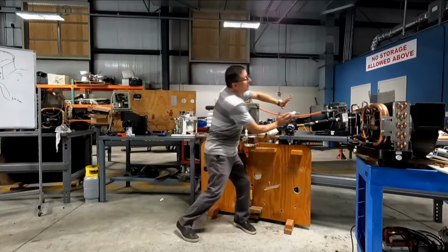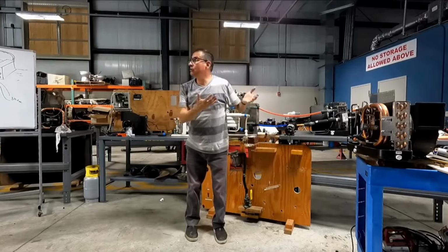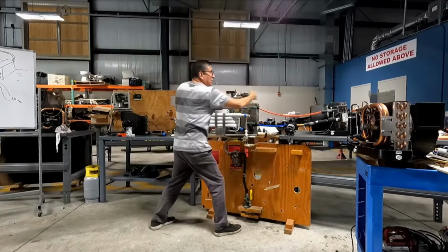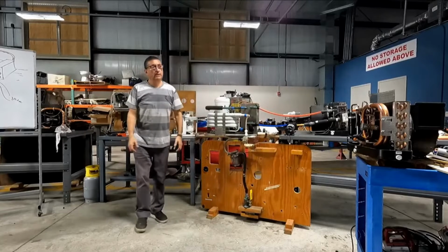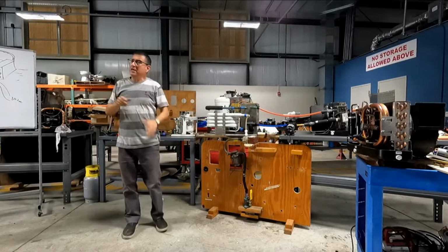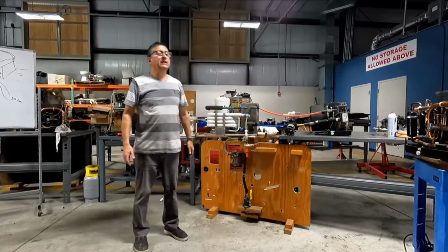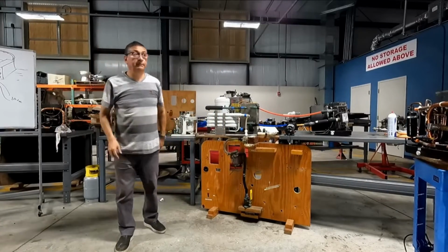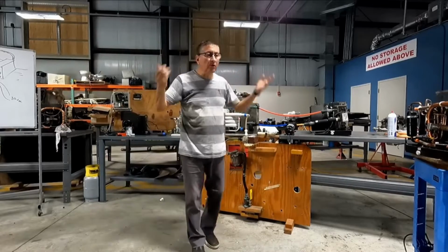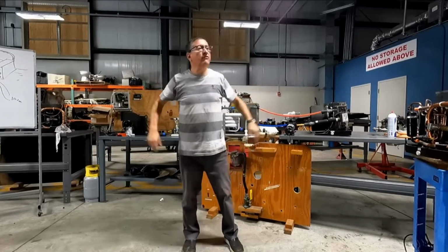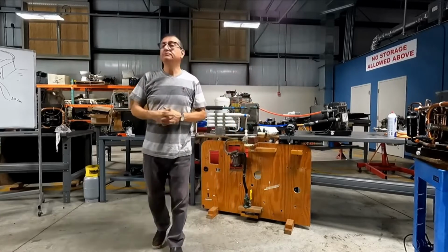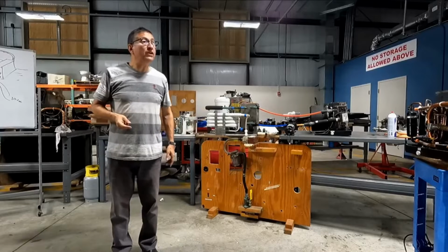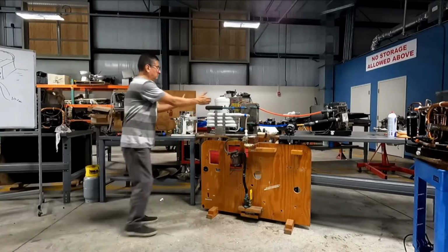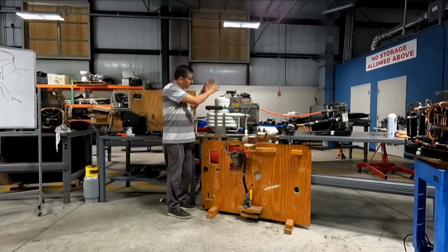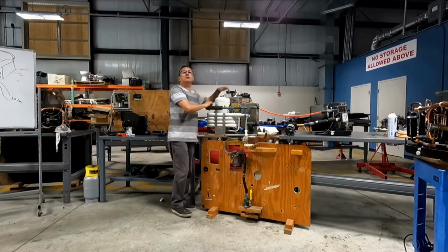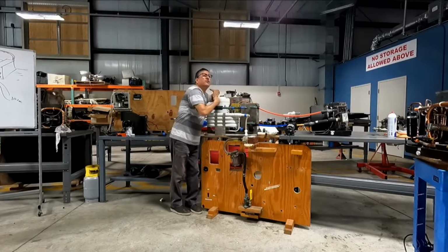What's the advantage? What is the name of that unit? Air handler. And what is the name of this complete unit? Chiller unit. The chiller system. Everybody follow me? Yes. Okay. Some people say a chiller unit is wonderful because I only use fresh water. I don't use refrigerant. Is that true? No. Do you use refrigerant? Yes. Where? In the compressor. Here, in between both of them. This is the compressor, compressed, passes to the coil, and returns. Yes or not? Yes. I have a self-contained unit.